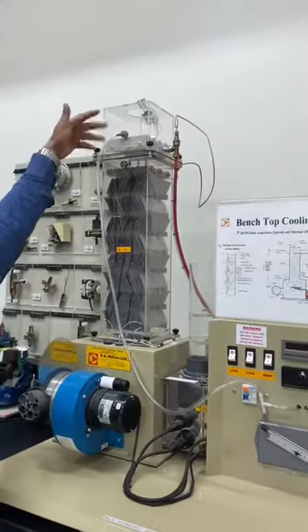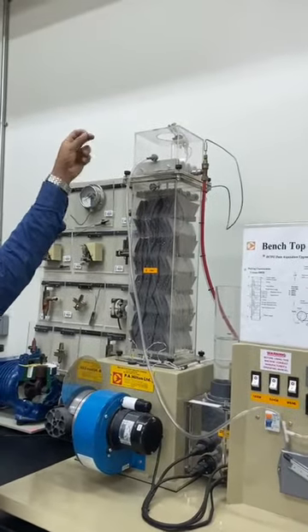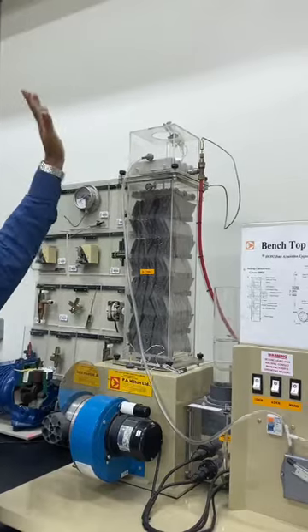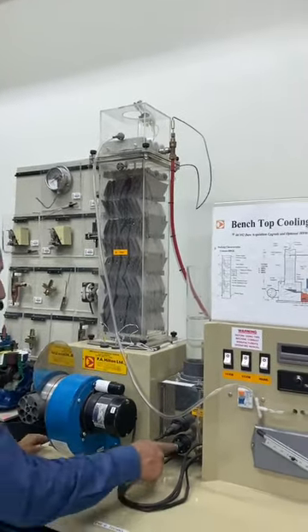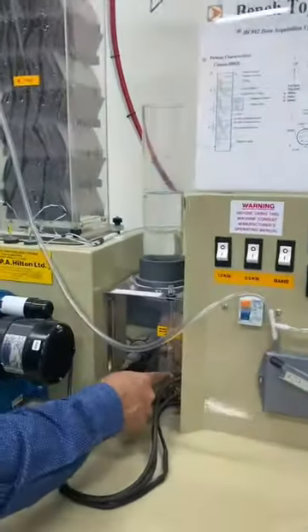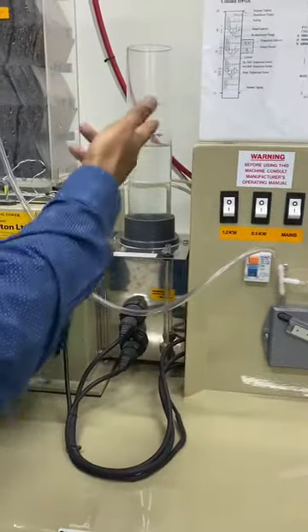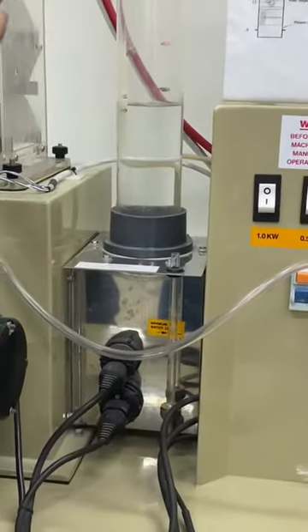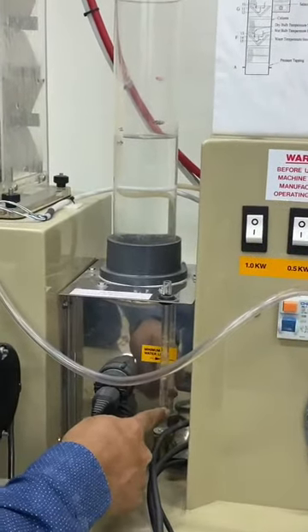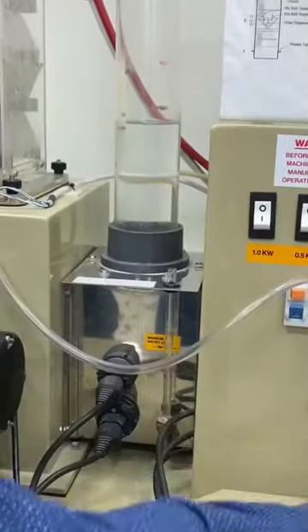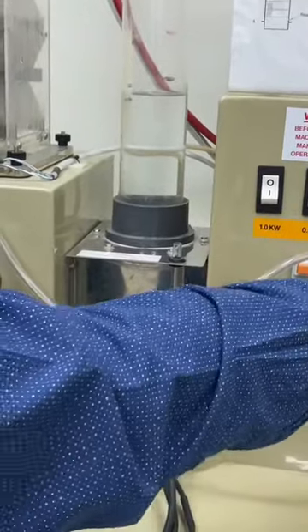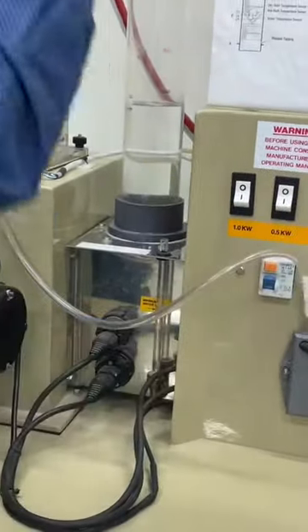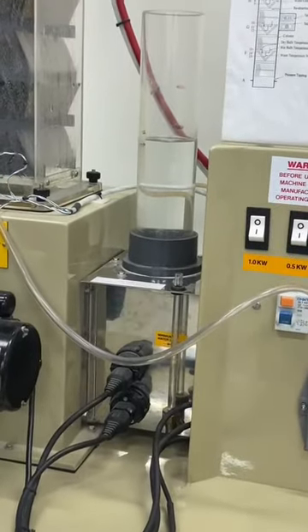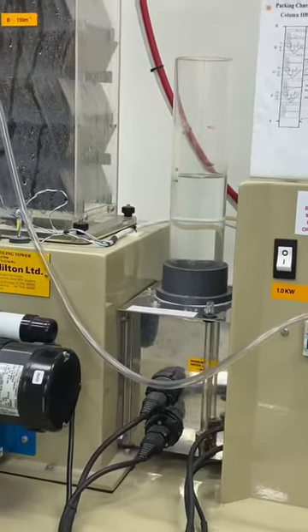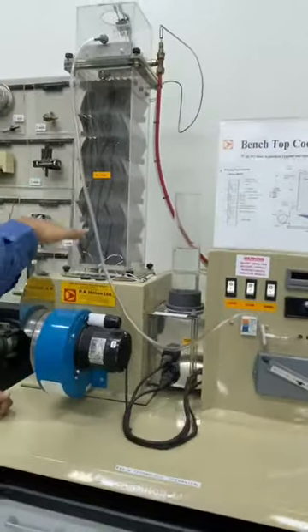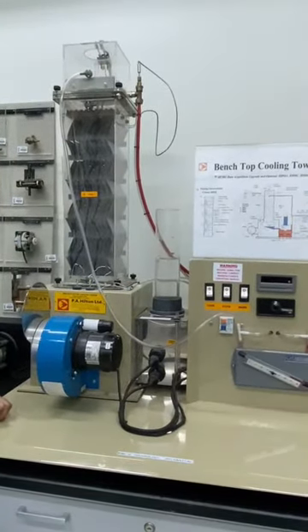And the hot air will escape with the water particles through the top. That is the bottom part. And here there is a float valve also. This float valve is actually to control the level of water in the tank here, to supply water to the cooling tower. And then this is the electric control system, temperature control system also here. This is a temperature knob, for controlling the temperature of the incoming supply water to the pipe, where there are a lot of nozzles to spray water to the inside of the cooling tower. These are the important parts.